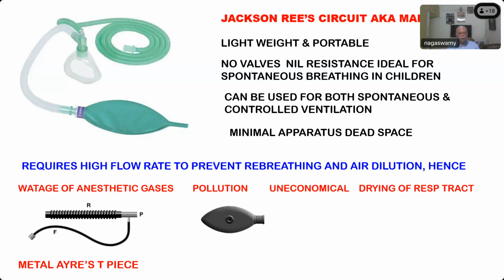What is this? The reservoir bag. Is there any peculiarity of this bag that you see here? Do you find anything unusual in this bag? Color of the bag. Opening. Open, this is an open end. Actually, because of the photo you can't see it there, but Jackson-Rees described that the reservoir bag should not have any valve at all. But nowadays we are putting a white plastic valve to adjust the filling of this bag. That should not be done.